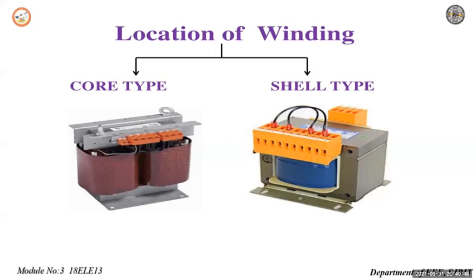It has a double magnetic circuit. The core has three limbs. Both the windings are placed on the central limb. The core encircles most part of the windings. The coils used are generally multi-layer disc type or sandwich coils.